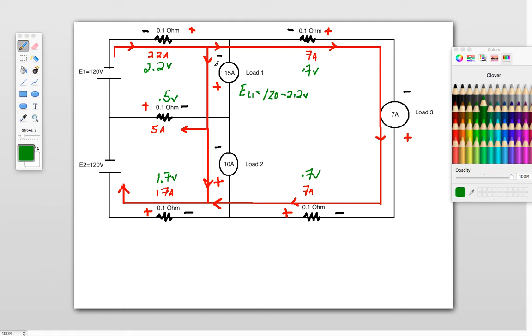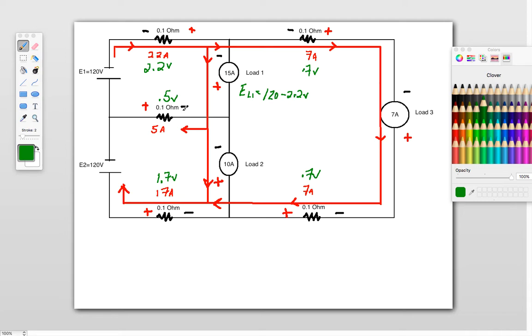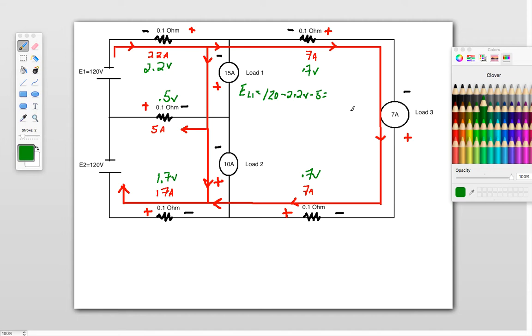And then at this point here, I don't have anything. This is what I'm solving for, so now I'm going to follow the current lines, so this potential here, it's connecting through here, so I've got a minus 0.5 volts here as well, because I came to the negative first. So my voltage at load 1 is going to be equal to 120 minus 2.2 minus 0.5, which is equal to 117.3 volts. That would be my voltage here.